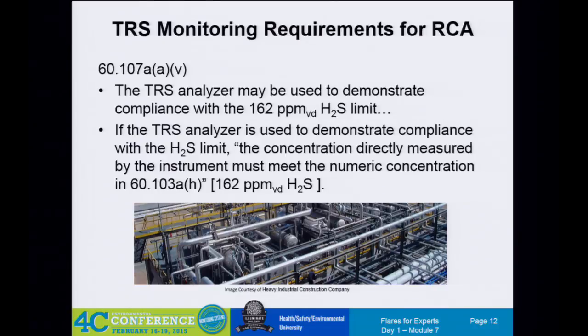It's effectively, as I said earlier, de facto total sulfur analysis. It's like pyrolysis tube analysis. But the people I've talked to say it's written for low BTU gases, and if you test it using high BTU gases, there are safety issues where you have to combust it all, and so you can't follow that method on a flare gas system.